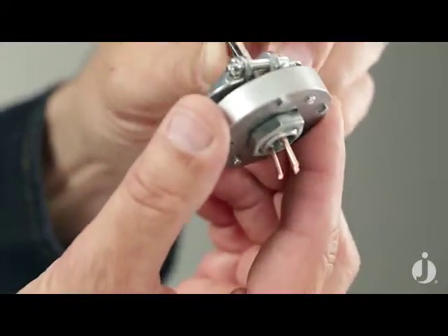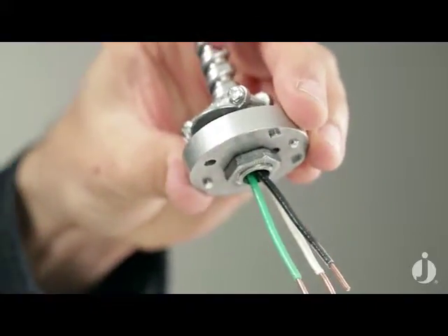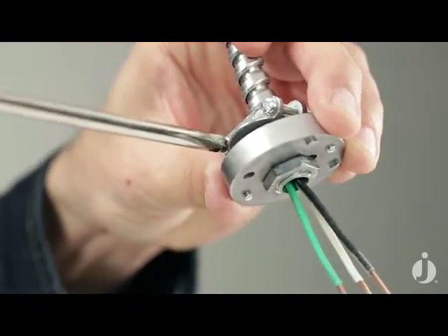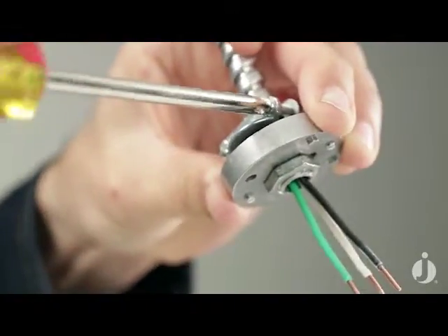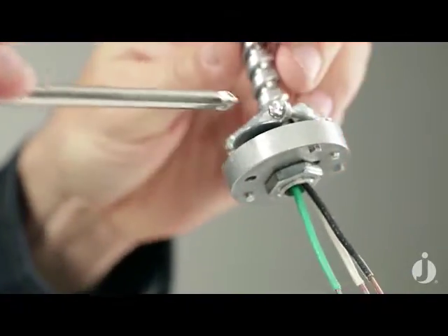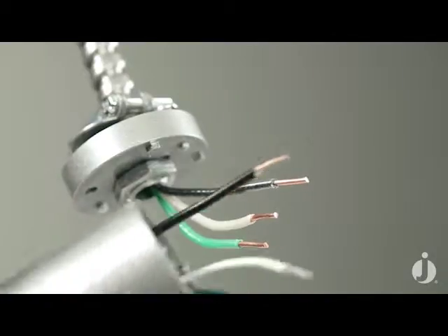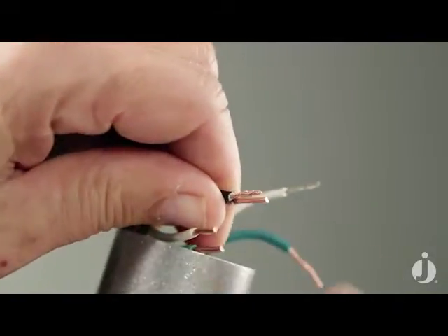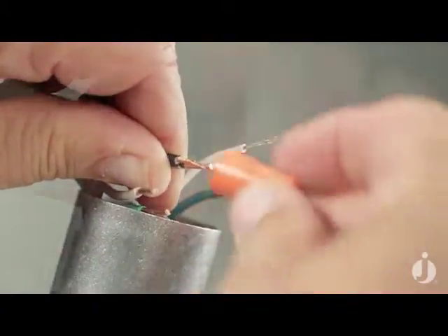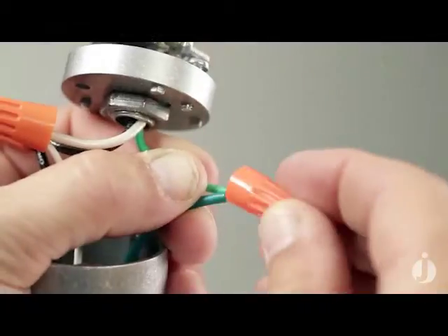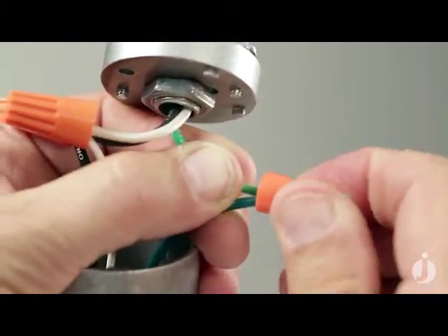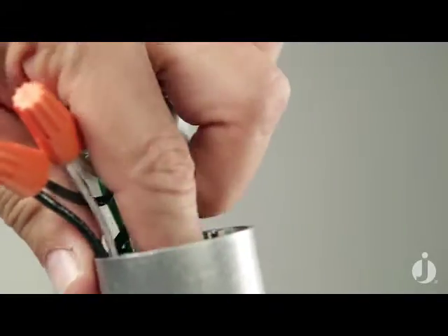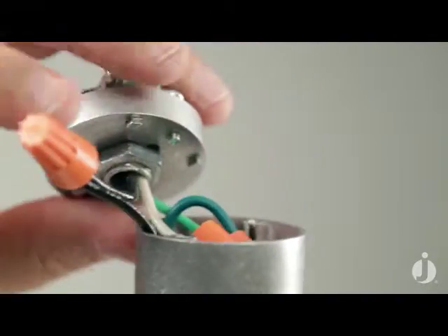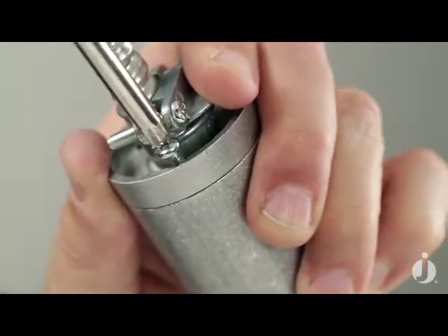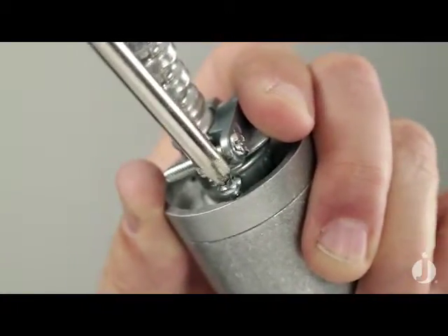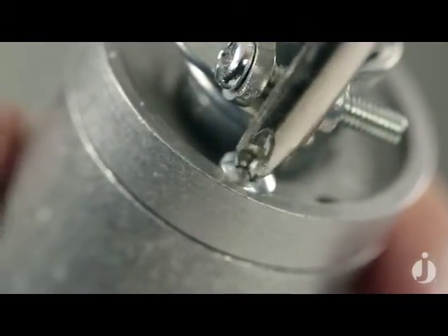installation. I'll feed that armored cable through my junction box cover, tighten the 2 screws that fasten the armored cable to the cover, and make sure that everything is nice and snug. Next, I'll bring my fixture over, and I'll fasten my black to my black, twisting on my wire nut. I'll fasten my white to the white, and my green to my green, my ground connection. Carefully then, I'm going to push those wires back into my wiring chamber with the transformer. Next, I'll fasten my cover to the back of that transformer cavity and tighten those 2 screws.